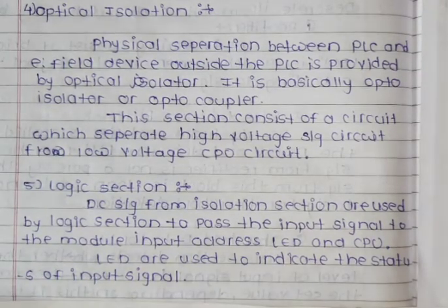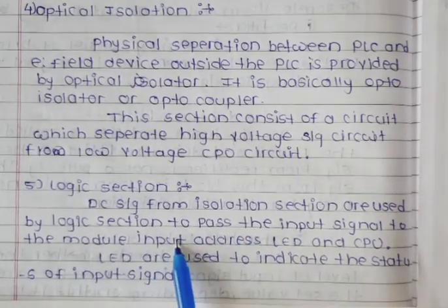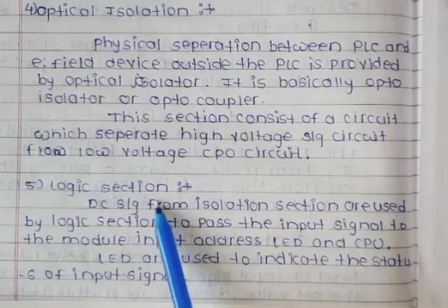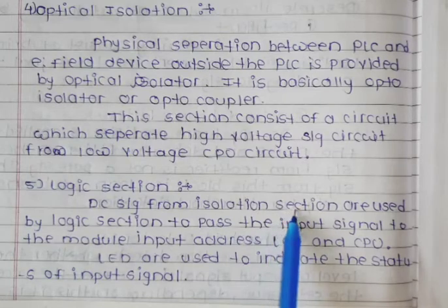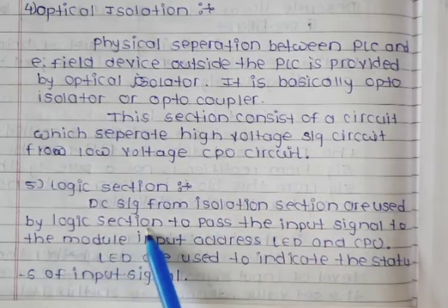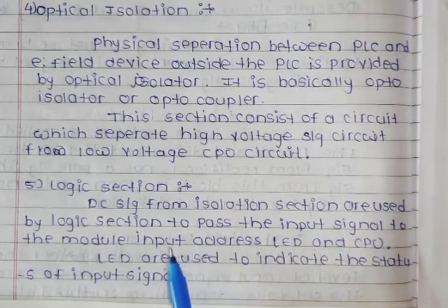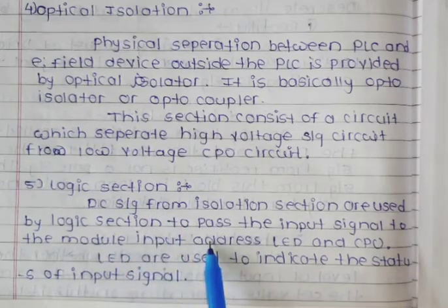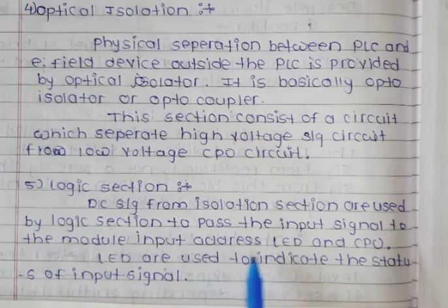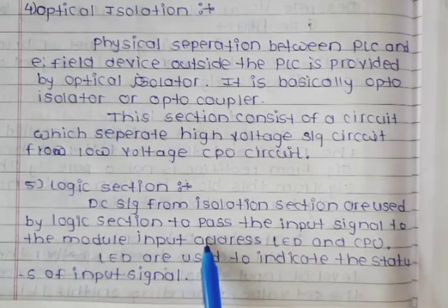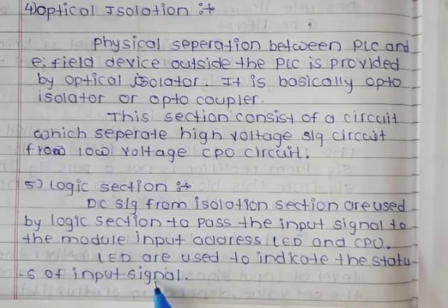In the logic section, the DC signal from the isolation section is used by the logic section to pass the input signal to the module input address, LED, and CPU. The isolation section supplies the DC signal, which the logic section uses to pass the input signal to the module input address. The LED is used to indicate the status of the input signal.